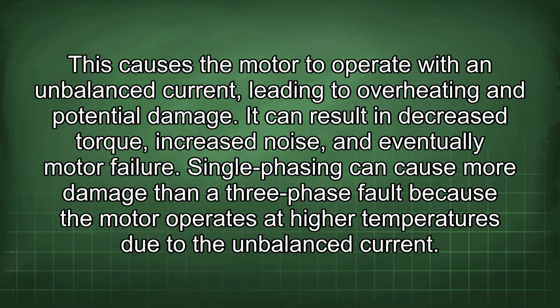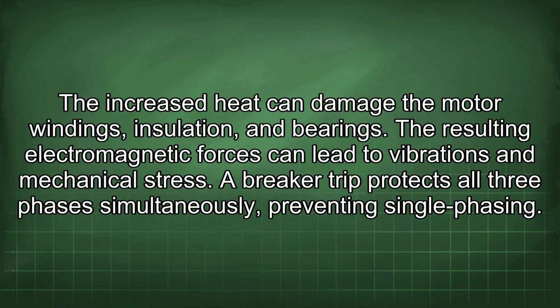It can result in decreased torque, increased noise, and eventually motor failure. Single phasing can cause more damage than a three-phase fault because the motor operates at higher temperatures due to the unbalanced current. The increased heat can damage the motor windings, insulation, and bearings. The resulting electromagnetic forces can lead to vibrations and mechanical stress. A breaker trip protects all three phases simultaneously, preventing single phasing.